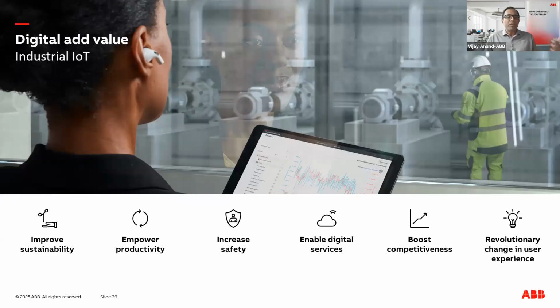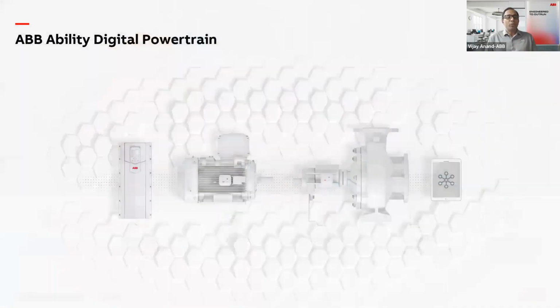So if this is where the water and wastewater industries are going, what can ABB offer to support them in this endeavor? So ABB offers to our water and wastewater customers who are looking for saving costs, run machines efficiently and reliably. The answer from ABB is the ABB Ability Digital Powertrain. So what is this offering? This is a suite of digital services which covers the variable frequency drive, the ABB drives, the electrical motors, it can be an ABB motor or any manufactured motor, and the driven system such as the pump or a fan or gearbox. So this system helps a user to understand the health and operating condition of the entire powertrain so as to take correct maintenance decision at the correct time.